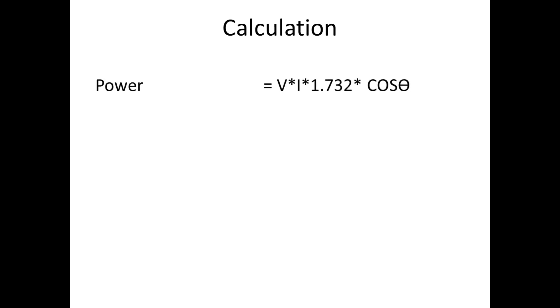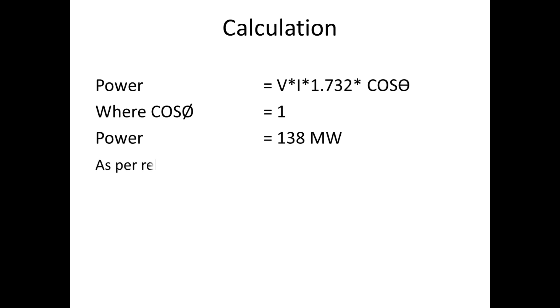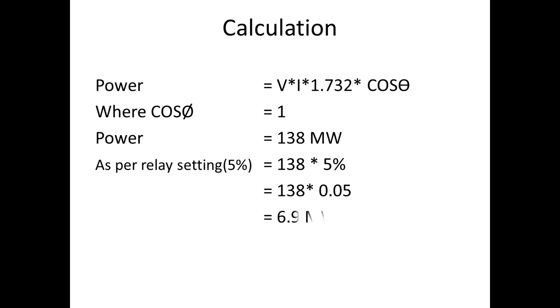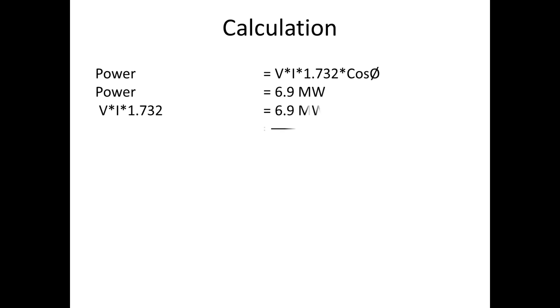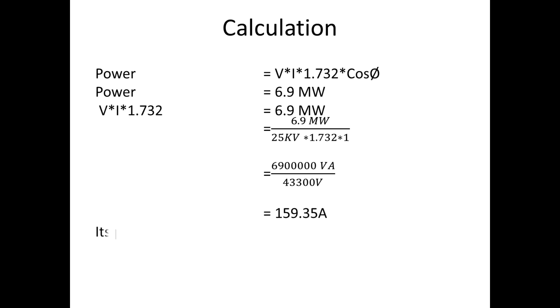Now we go for calculation. We all know the formula for power is V × I × 1.732 × cos θ, where the value of cos θ is 1. The generator power is 138 megawatt. As per relay settings it is 5 percentage, so we have to multiply 5 percentage with generator power — 5 percentage is 0.05 — and we get 6.9 megawatt. We have to equate this 6.9 megawatt into the power formula. As per low forward power, it mainly occurs with low current, so here we are going to keep voltage constant at 25 kV. In this formula, keeping current on one side and all remaining on the other side in the denominator, when I substitute all the values I got 159.35 amps.